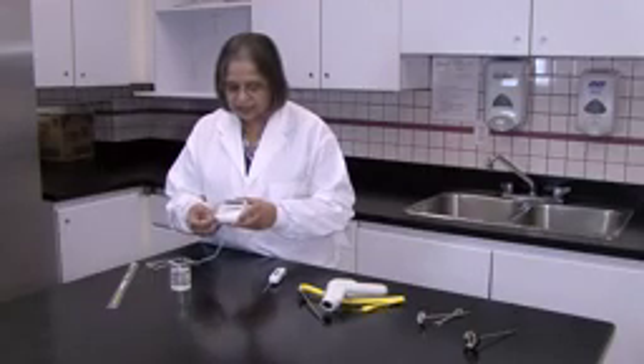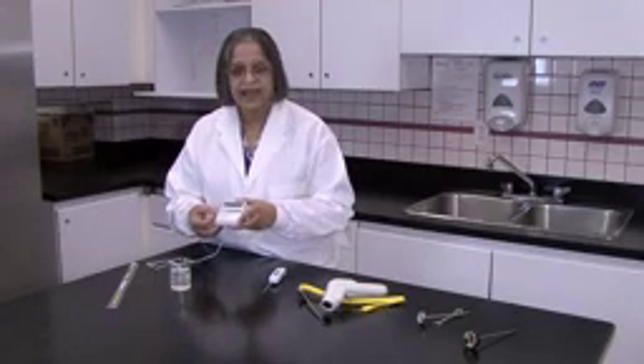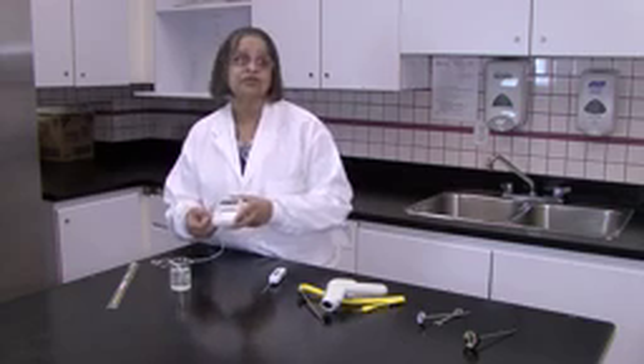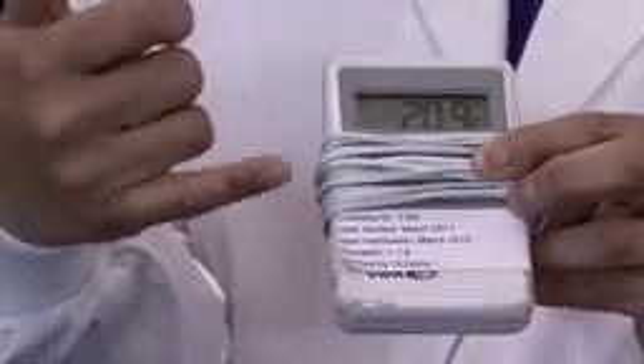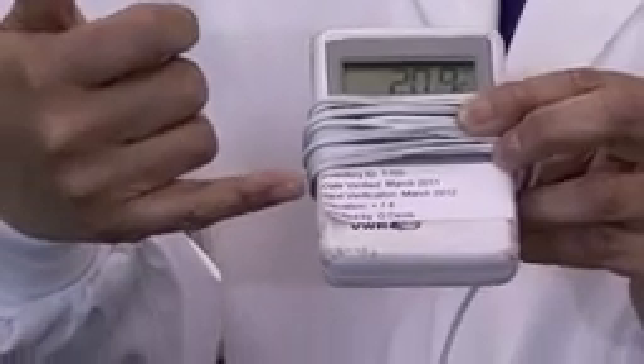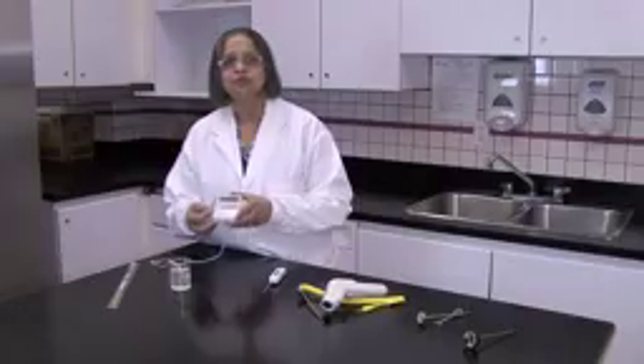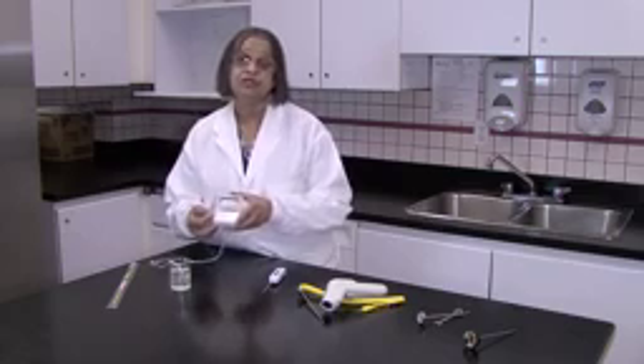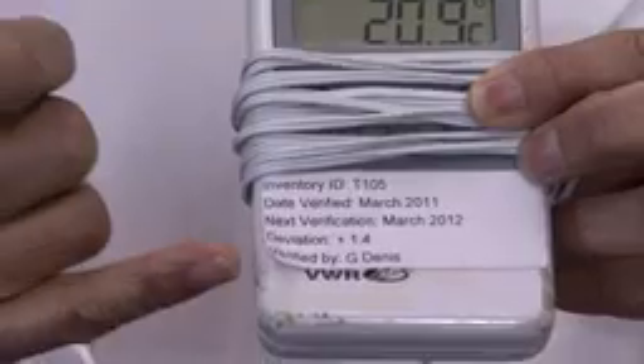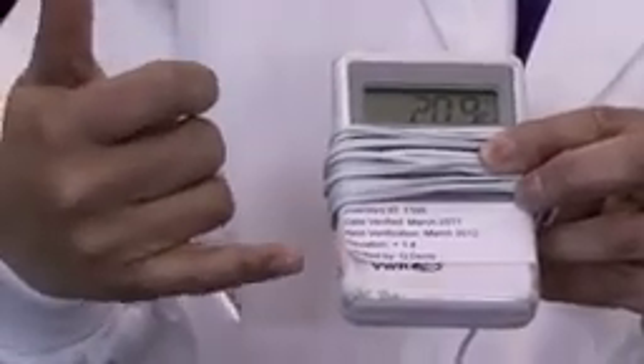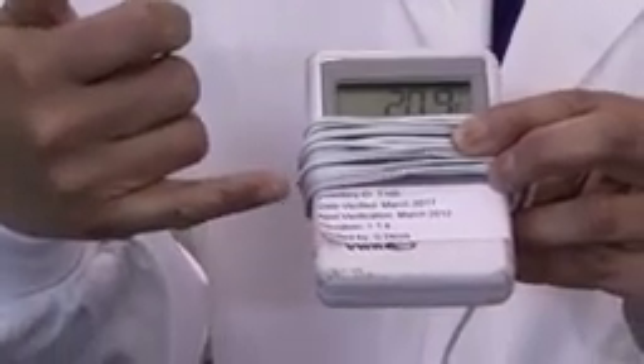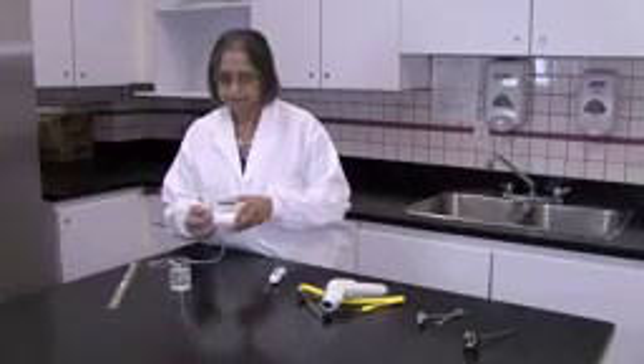Another thing on this that is important is that the label indicates the date that it was calibrated. It has a unique inventory number. It has the date that it was calibrated, the date that we need to calibrate it again, the deviation of 1.4 degrees, which means that it reads 1.4 degrees higher than we would expect, and who verified it. This information may be recorded on the label as shown here or in a calibration log.